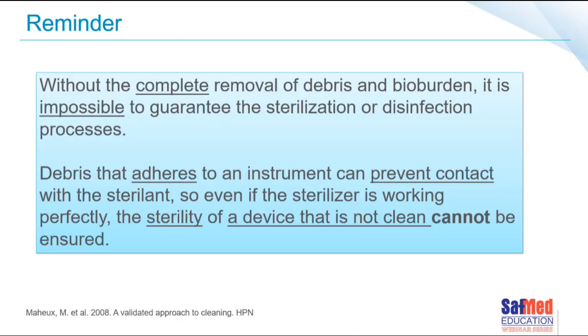Without complete removal of debris and bioburden, it is absolutely impossible to guarantee the sterilization or disinfection of any instruments. Debris that adheres to an instrument can prevent contact with the sterilant. So even if the sterilizer is working perfectly, the sterility of a device that is not clean cannot be ensured.